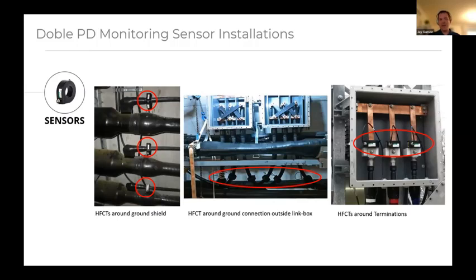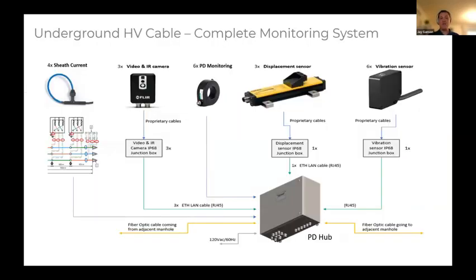So we've evolved the PD design to actually include multiple sensors and multiple inputs that could bring in other parameters. For example, right next to where we put on HFCTs to get information about partial discharge, we can also use Rogowski coils to get information on the current traveling through the grounds into the cross-bonded link box. This is really useful because now we can provide information about: is the cross-bonding link box working properly? Are we grounding out any induced currents or induced voltages on these cable runs?